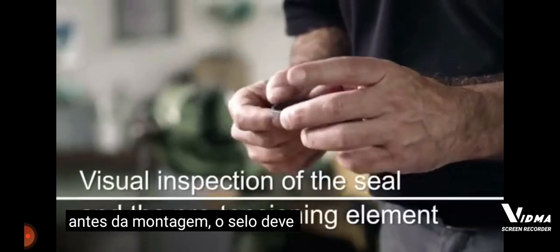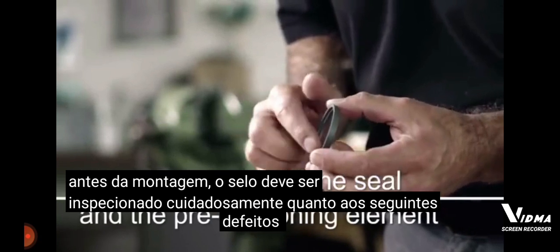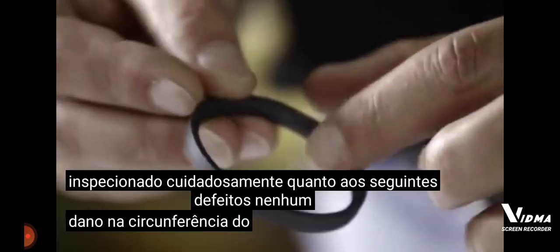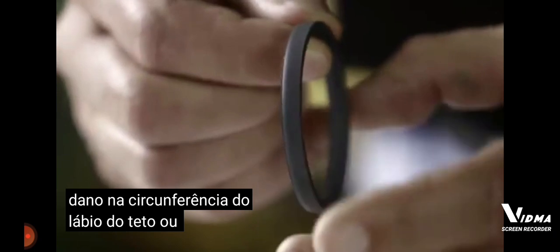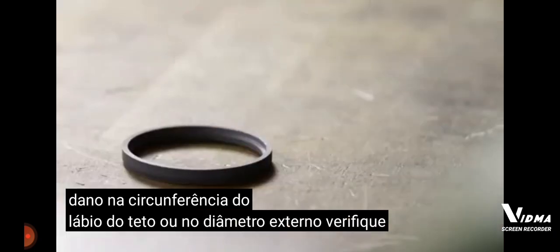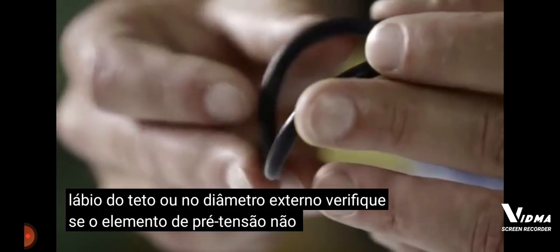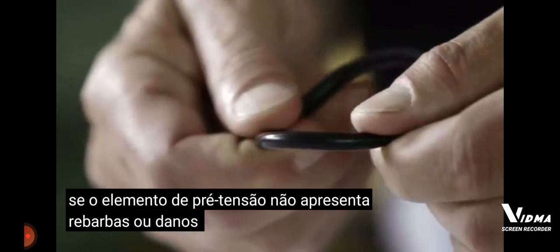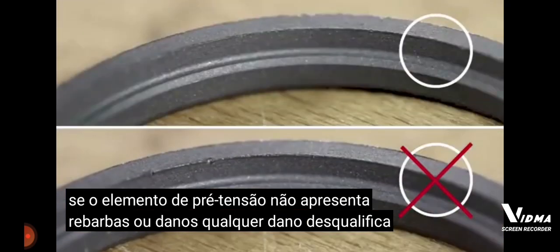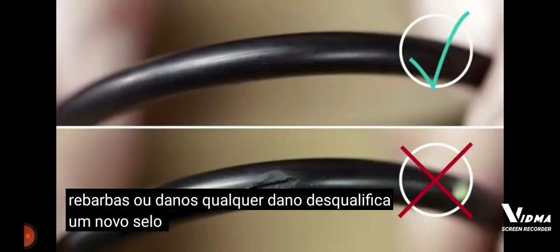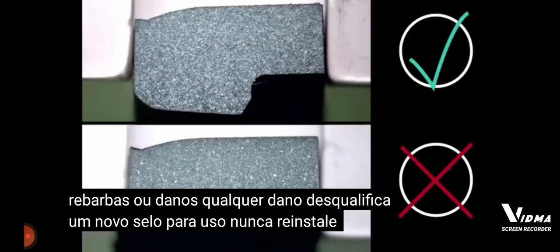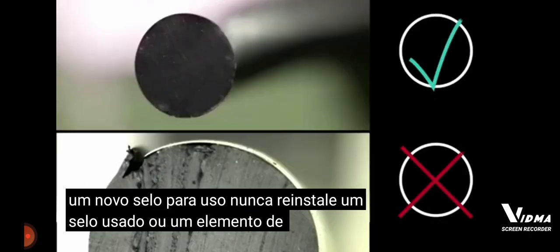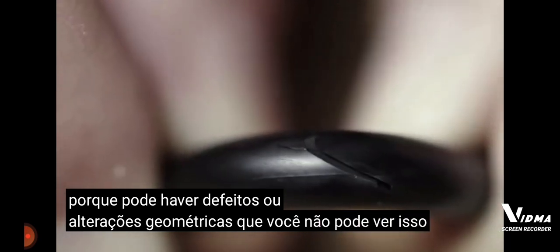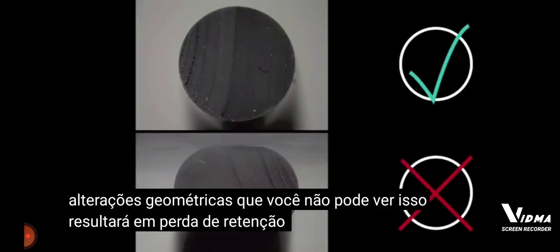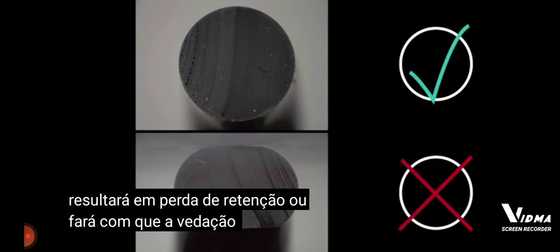Before assembly, the seal must be closely inspected for the following defects. No damage on the circumference of the sealing lip or the outer diameter. Check that the pre-tensioning element has no flash or damage. Any damage disqualifies a new seal from use. Never reinstall a used seal or a pre-tensioning element because there may be defects or geometrical changes you can't see. This will result in a loss of pre-tension or cause the seal to fail.